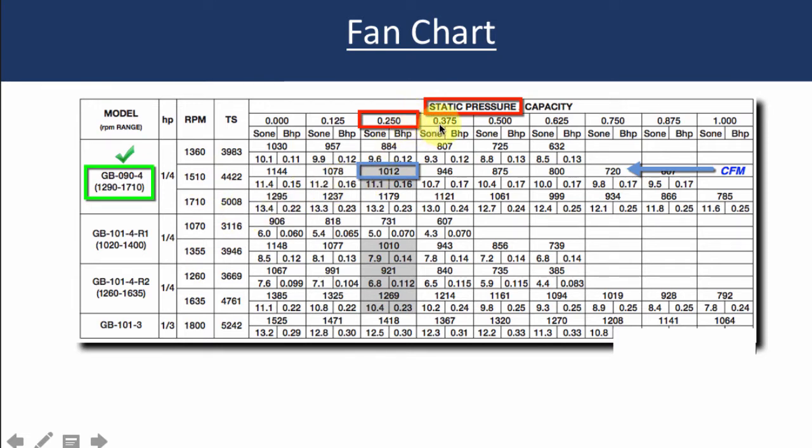Now as you can see, as your static pressure goes up going to the right here, for the same fan at the same speed, you start to lose CFM. Your flow, your CFM is getting eaten up by this increase in static pressure.